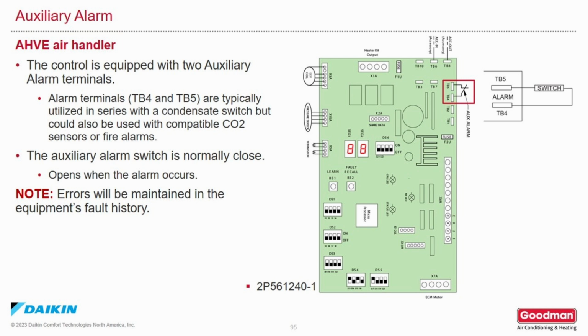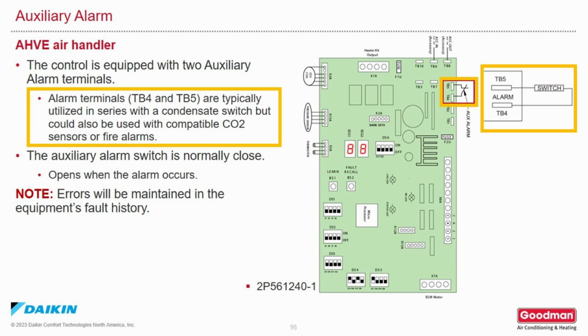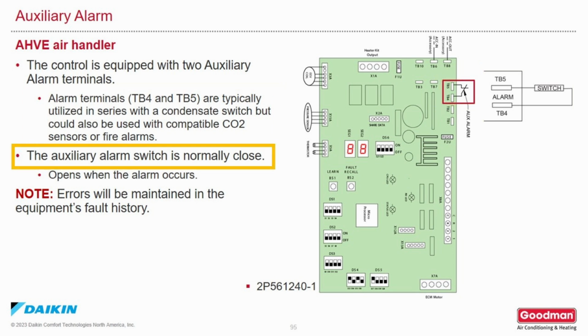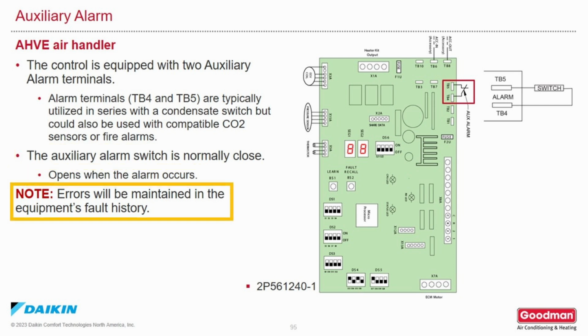The auxiliary alarm for the AHVE air handler. The control is equipped with 2 auxiliary alarm terminals. Alarm terminals TB4 and TB5 are typically used in series with a condensate switch, but can also be used with a compatible CO2 sensor or fire alarm. The auxiliary switch is normally closed. Alarm occurs when the switch is opened. Note that errors will be kept in the equipment's fault memory.